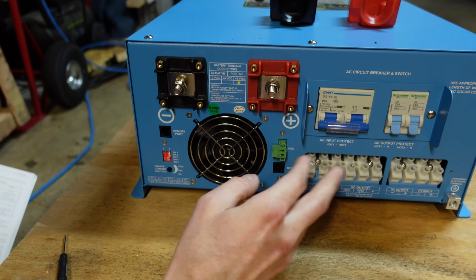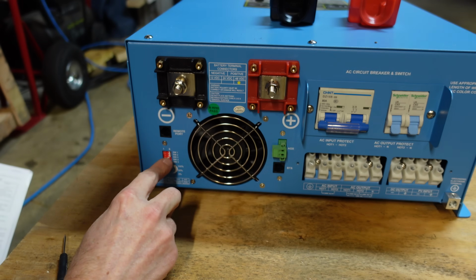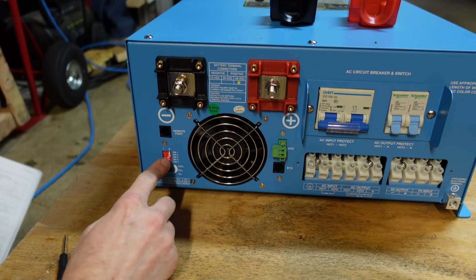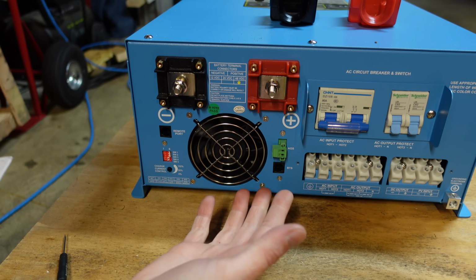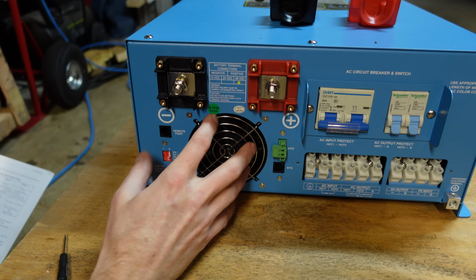The first thing I want to do before connecting the battery positive and negative and the AC output is to make sure these DIP switches are set correctly. I'm not going to be testing the AC input or MPPT charge controller in this video. This is simply testing the output of the inverter itself as an off-grid standalone system.